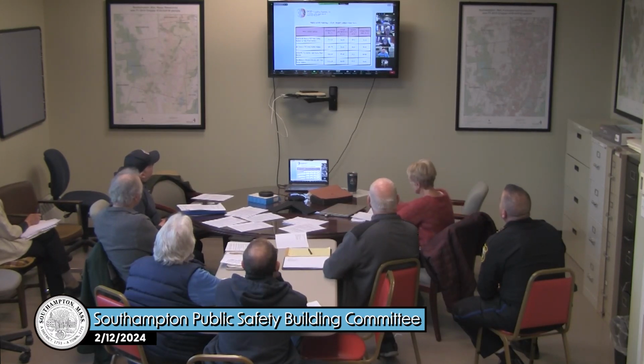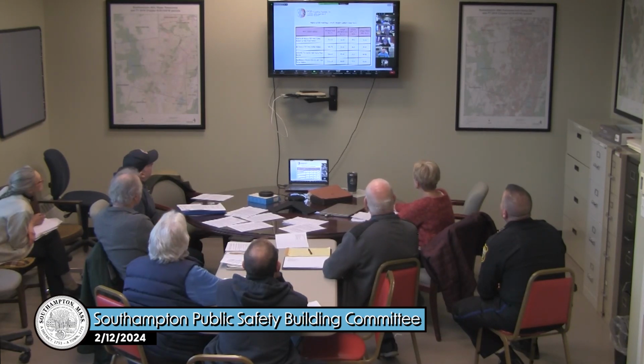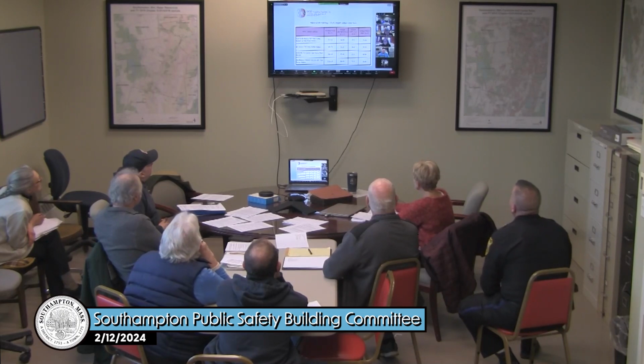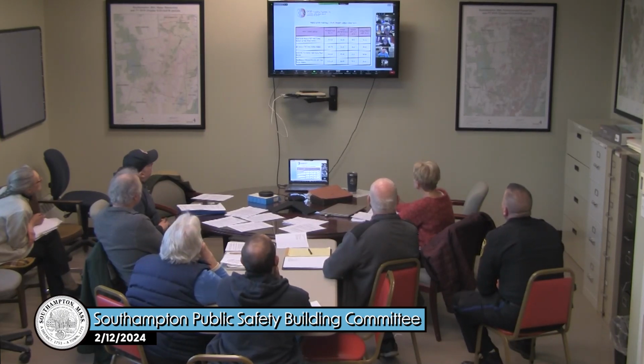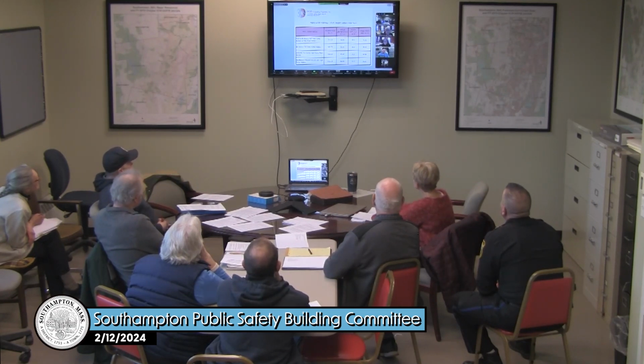So this is kind of like what the LCCA will show for a hybrid system, or if we do an air source VRF paired with a boiler to provide supplemental heating. It's going to have one install cost. This is really just to show a comparison between the different options. Obviously your geothermal at the bottom has a much higher install cost than the other options, but it does have a low EUI.